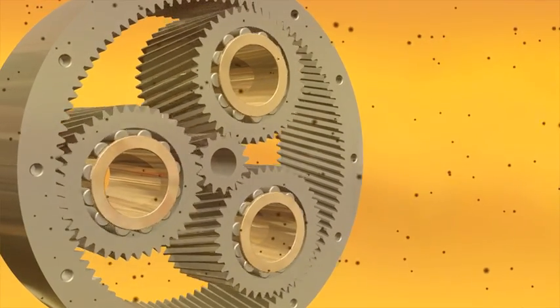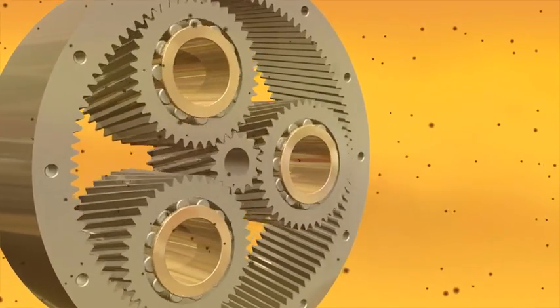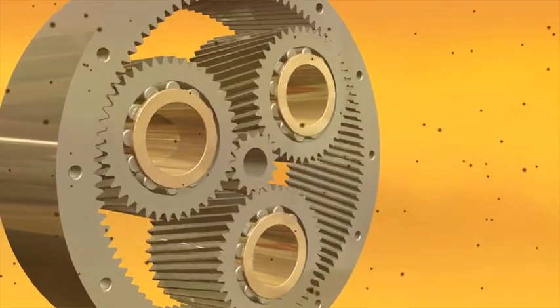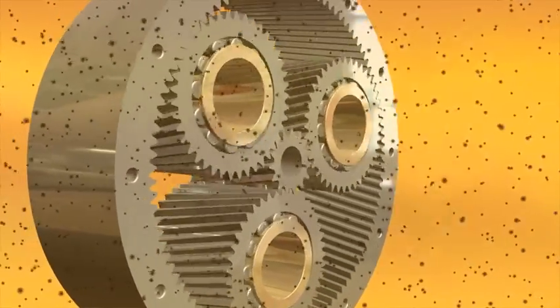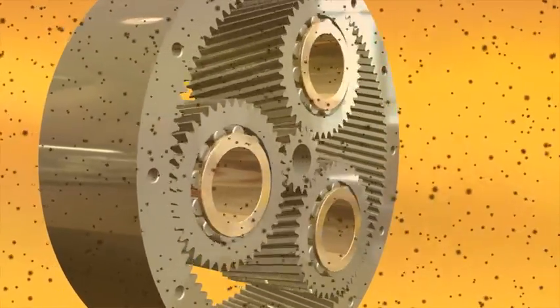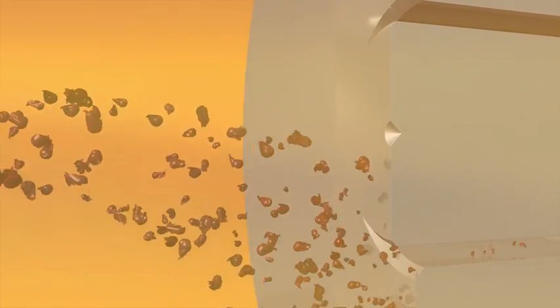Particles are constantly released from the gearbox components to the oil. Every change in operation condition generates a particle peak where millions of small micron particles are released. These need special attention as they are small enough to enter the very fine tolerance of the gearbox.